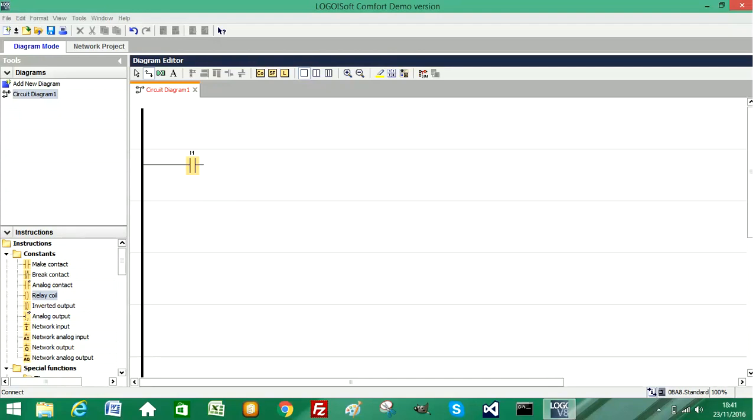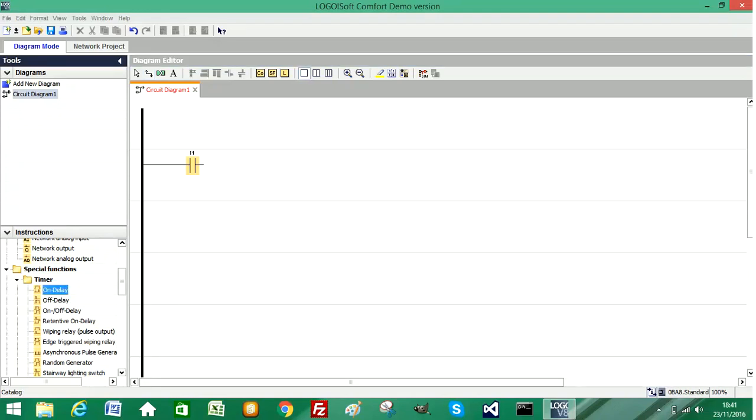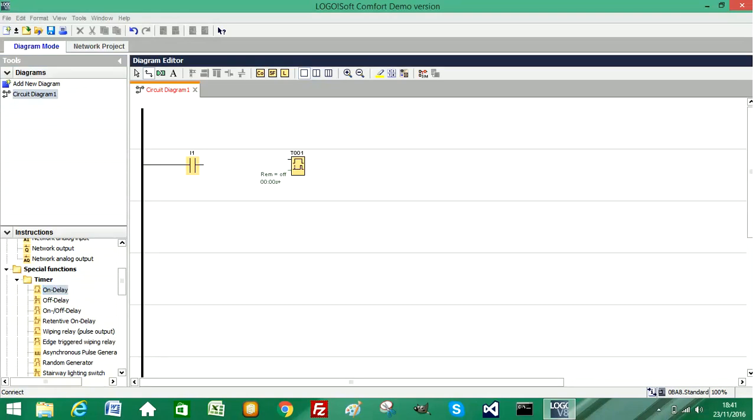If I scroll down on my list of options, I'm going to select the timer to use, which is an on delay timer and place it into my program. It gives it a name of T001. It will give each timer you add a unique name. If your timers had the same name, it would cause a conflict within your program.